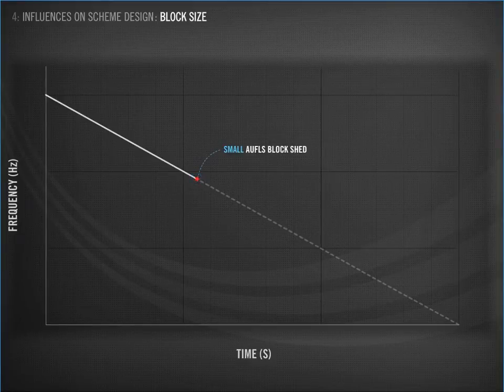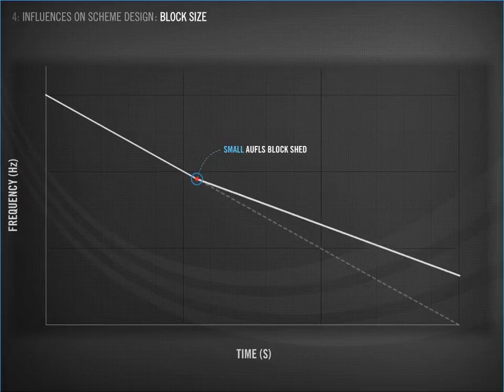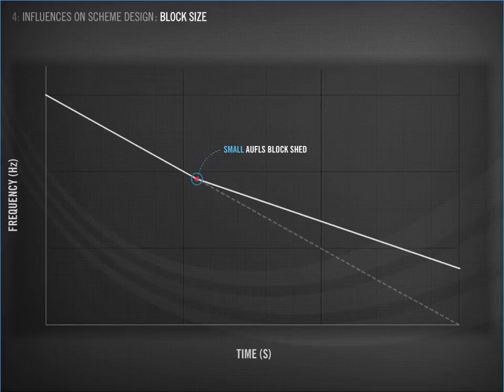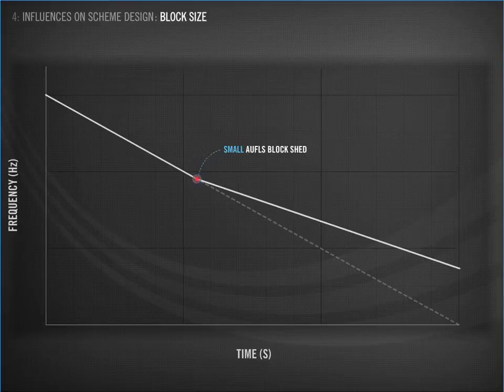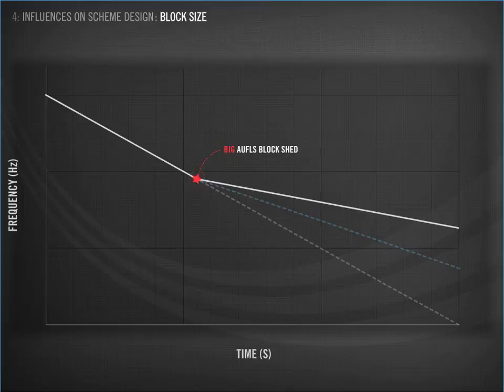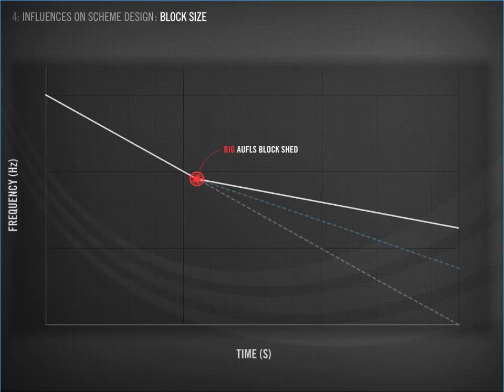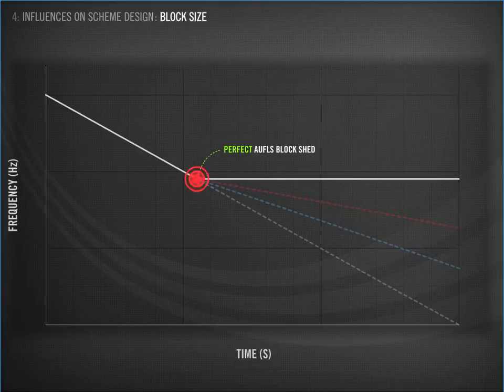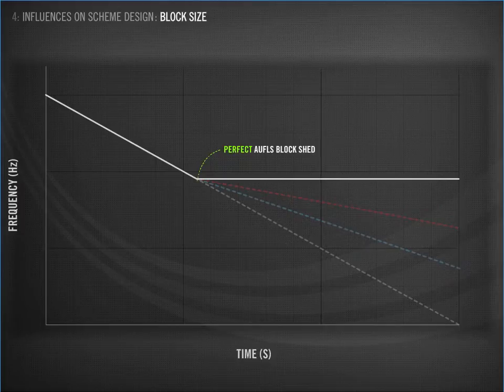Here we have disconnected a small amount of load from the system. This is like hitting the brakes in your car. Disconnecting this small load slows down the rate at which the frequency is falling. If you hit the brakes even harder, by disconnecting a bigger load, then you slow down even more. Here is a bigger AUFLS block, and you can see it has slowed the fall in the frequency even more. If we shed the exact amount the system needs at the time, the frequency stops falling and levels out. The generator's governors pick up and the frequency is returned to 50 Hz. This is the perfect response.